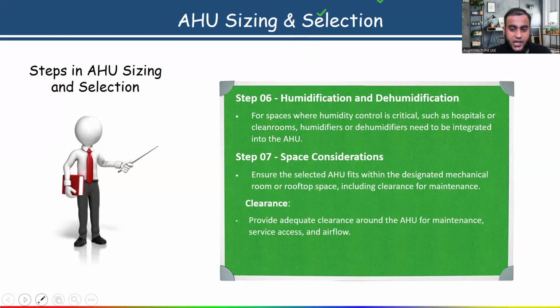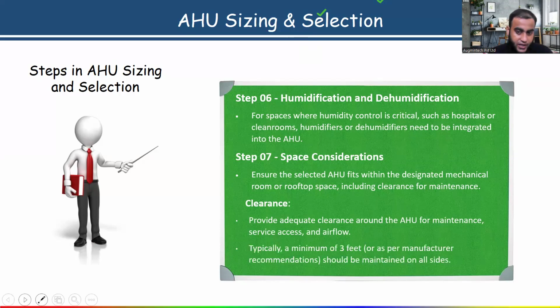Next, the clearance which we have to maintain is given. Provide adequate clearance around the AHU for maintenance, service access, and airflow. Here it is given as a minimum of 3 feet, and I am also doing it as per experience. For spacing, as per manufacturer recommendation, we have to maintain a minimum of 3 feet on all sides of the AHU, for maintenance purposes, service access, and airflow. 3 feet minimum clearance we have to maintain. Now, is this point clear? Tell me, please, give me a reply. Is this point clear, all of you? Okay.